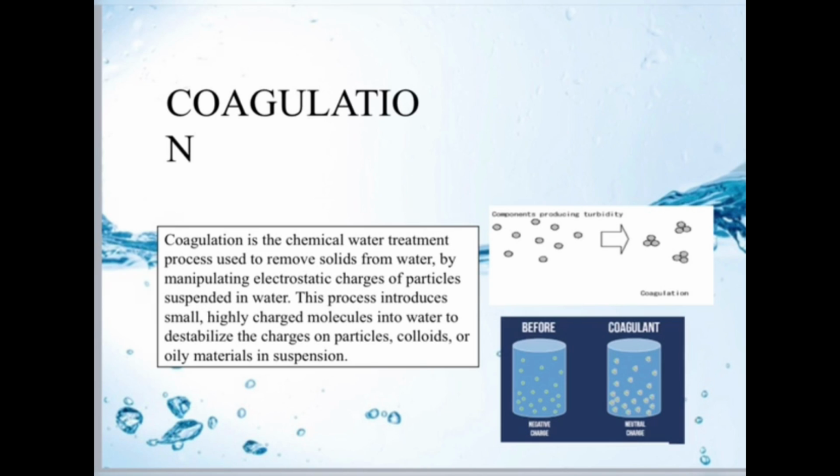In addition, the slightly larger particles formed through this process are called microflocs. A high energy rapid mix to properly disperse the coagulant and promote particle collision is needed to achieve good coagulation and formation of the microflocs.